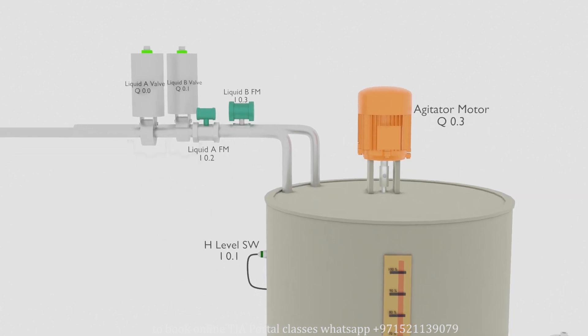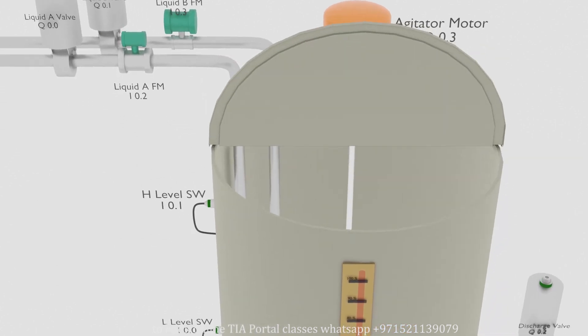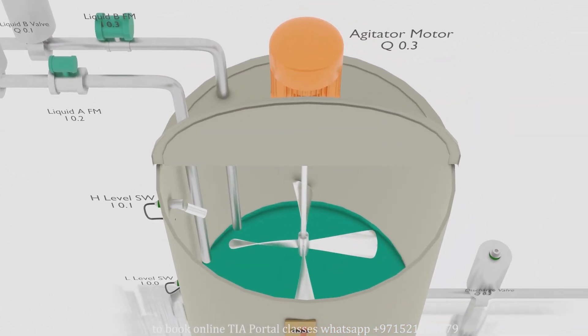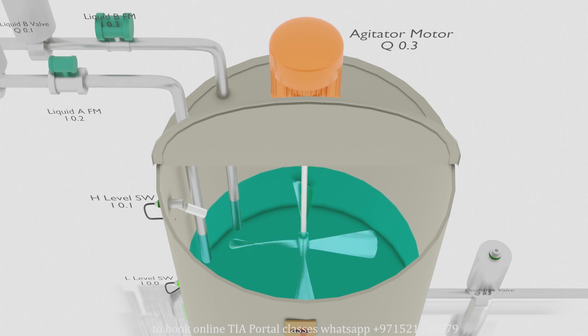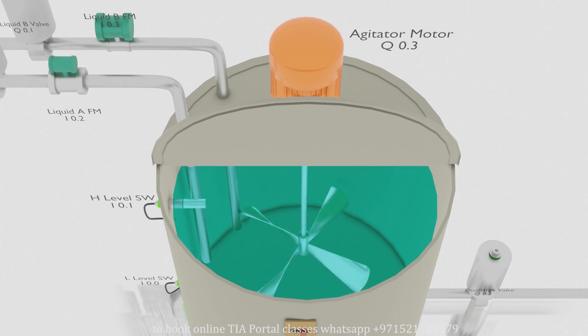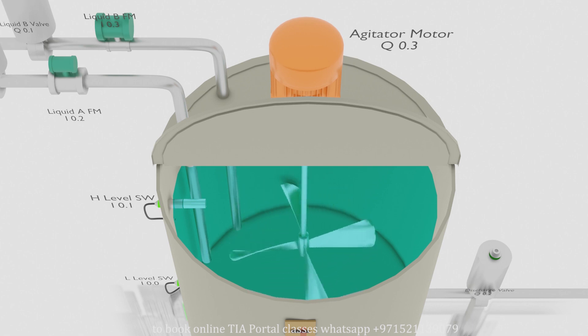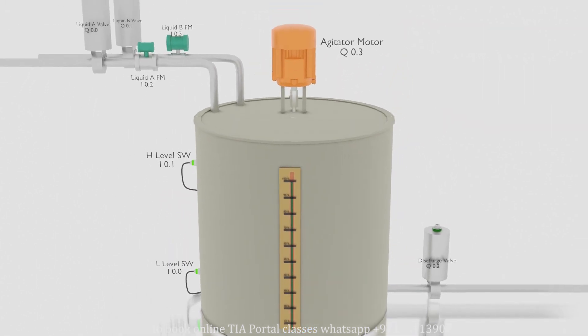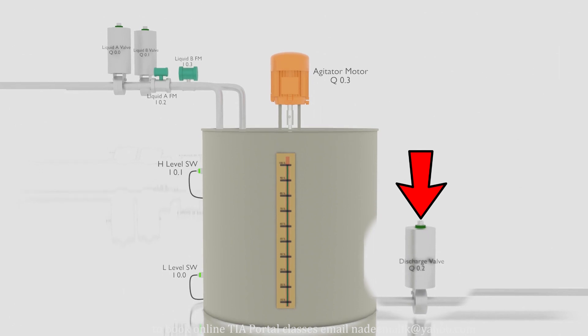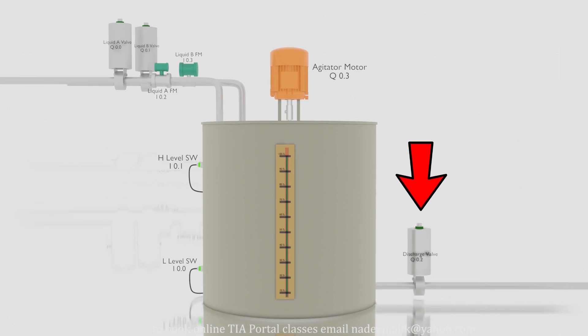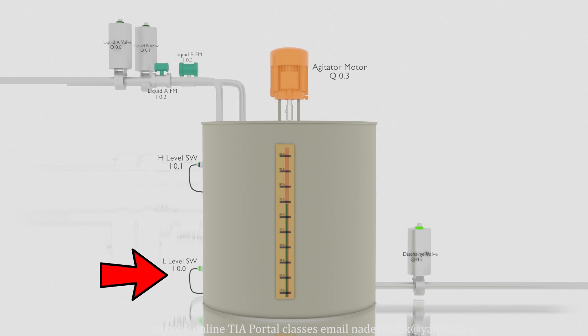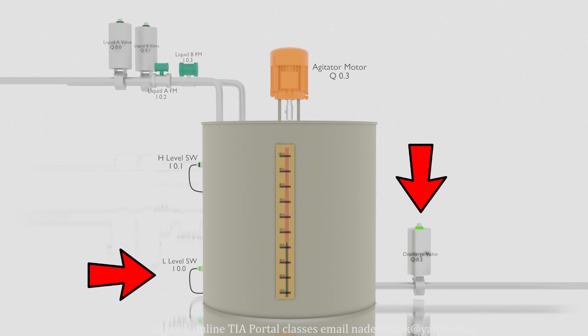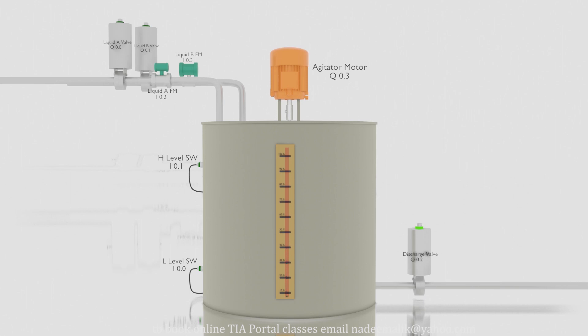As the flow meters confirm that 50 liters of liquid fill inside the tank from both sides, the agitator runs for 50 seconds to mix these two liquids. After 50 seconds the agitator stops and discharge valve Q0.2 opens and starts to discharge the tank. As the liquid level drops below the low level probe I0.0, the drain valve Q0.2 closes and stops draining the tank. And the whole process will once again start to make a new batch of these two liquids.